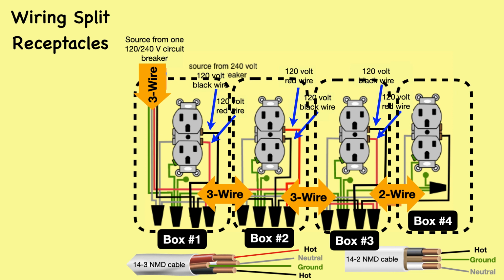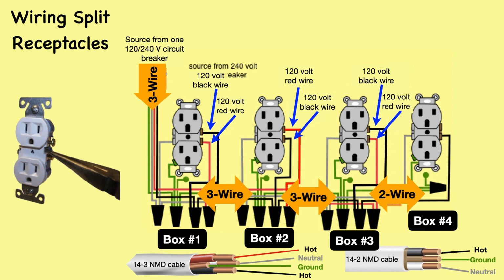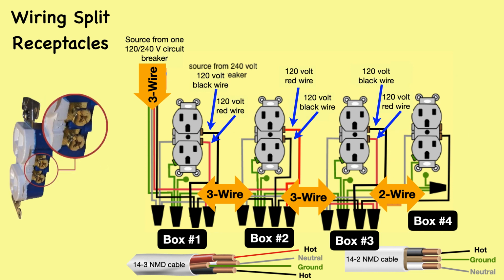The 2 hot screws on the receptacle are joined by a breakable solid connection. This solid connection can be twisted off with a pair of pliers, separating the 2 brass screws. This is known as a split receptacle. Each plug on a duplex receptacle is on a separate circuit, as indicated with the blue arrows in the diagram. Each can support 15 amps. Notice that the last duplex receptacle in the group is not a split receptacle. Hence, only one 14-2 cable needs to be run to this receptacle.